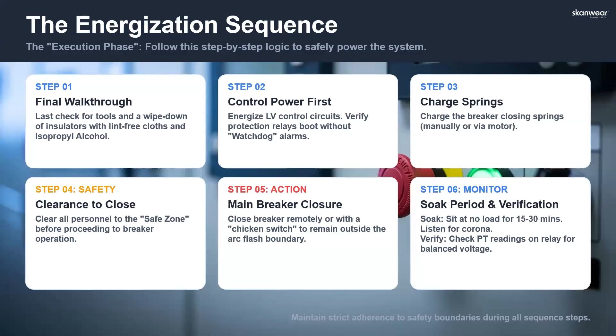For those of us not in the US, the chicken switch reference would be like a remote pendant, or an umbilical where you'd plug it in and take it outside of the substation to operate it from remote. Is there any context to why it's called a chicken switch, Wayne? I think because we don't do manual racking anymore, where folks are in there actually cranking that breaker in. We now have equipment that we can put in place and then energize to rack that breaker in or out without the worker being right there at the hazardous area. Yeah, perfect.